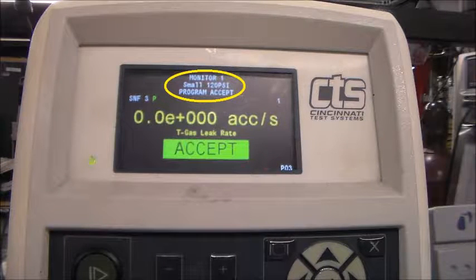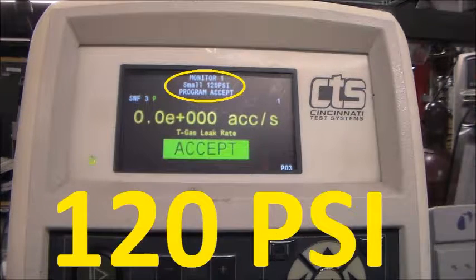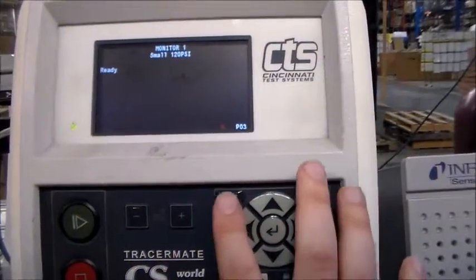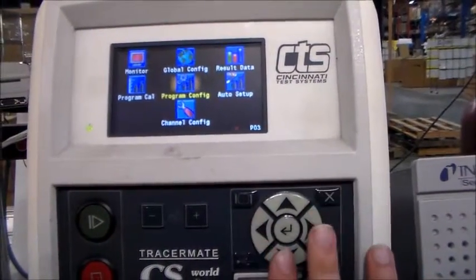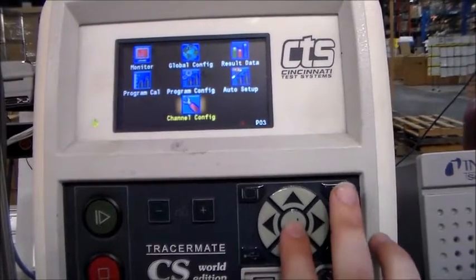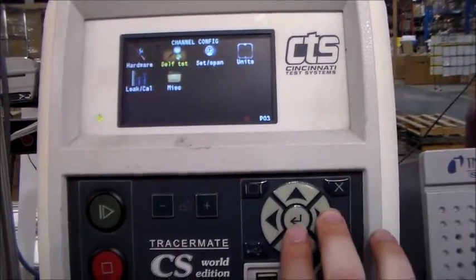For now, stick with 120 psi. 120 psi is the default for cores and tube assemblies using this machine. Return to the main menu screen when finished. Now we can run the self-test by pressing the menu button, selecting Channel Config, and then the self-test button after that.